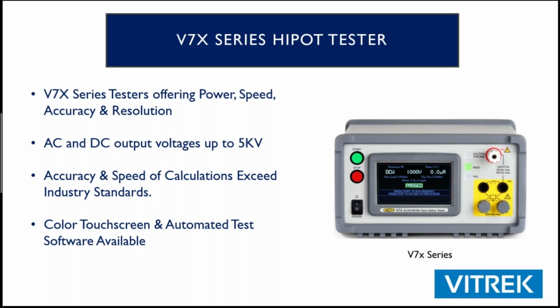It's highly configurable. There's 7 different versions of it, anywhere from AC only with continuity to AC DC insulation resistance and ground bond, all in the same product. If you're buying one of these in the early stages of design, I highly recommend going with the V74. That way you're going to have more testing options that are going to let you qualify your products and actually make sure that you're complying with these standards before you get to your production test.